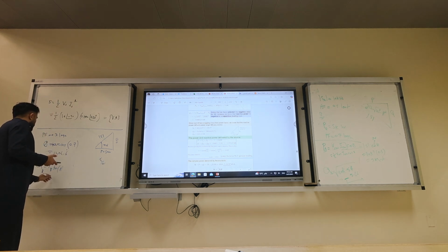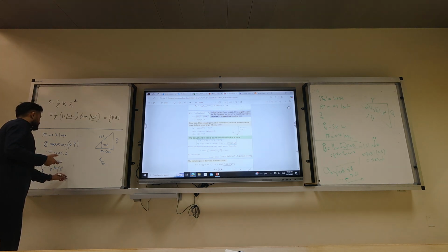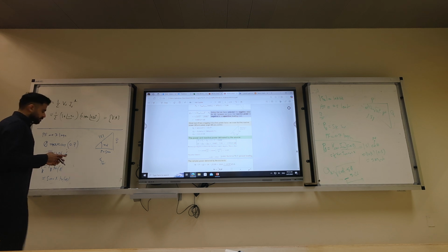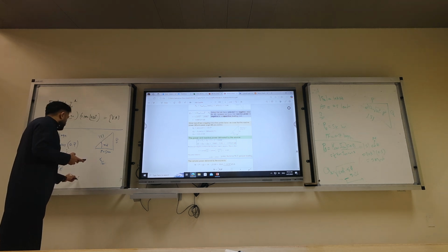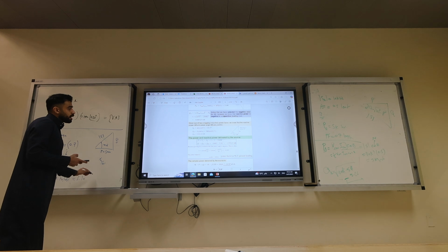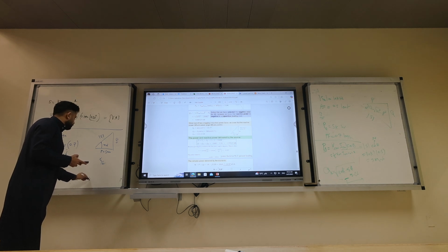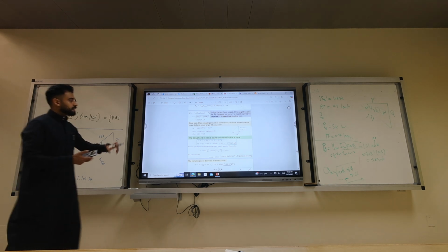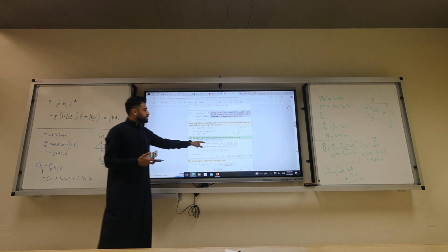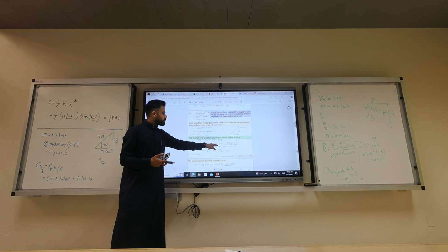So that's equal to 5,000 times tan of 45.6. That will give you the quantity 5.101 kilovars. Then I can know S easily.